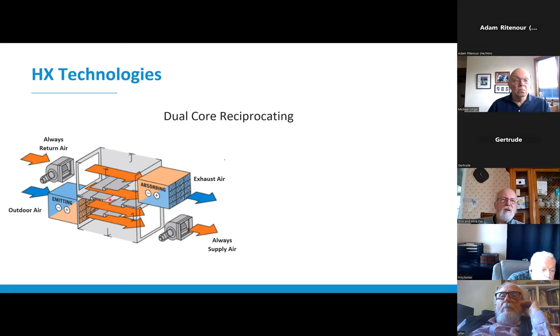redirect the air. So in this orientation, in this first graphic, you'll see that the return air is coming into the unit and going right across to this core. So it's charging this core with heat, and that exhaust air is coming out a little cooler. And at the bottom, the outdoor air is actually going through this emitting core, picking up heat and being supplied to the building.